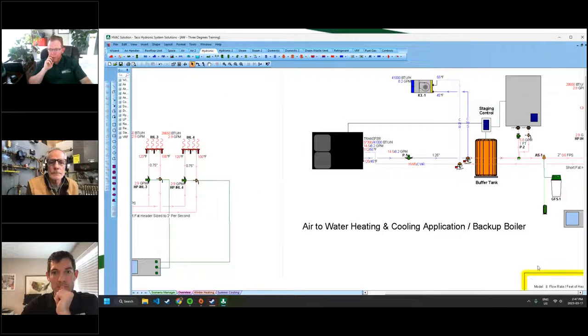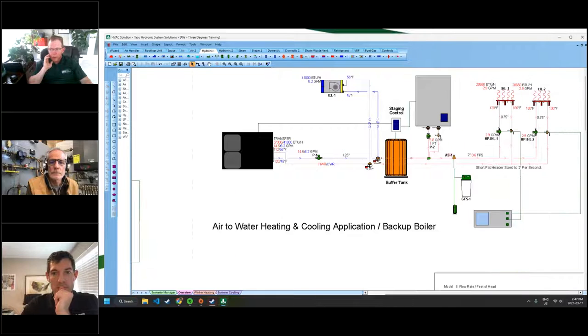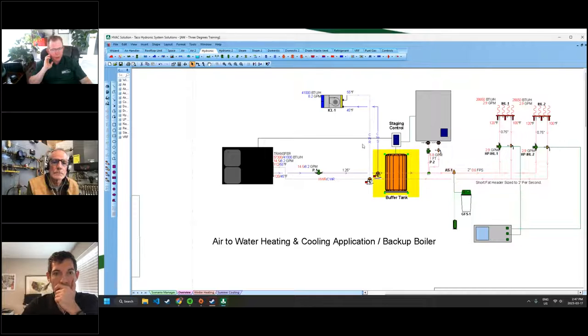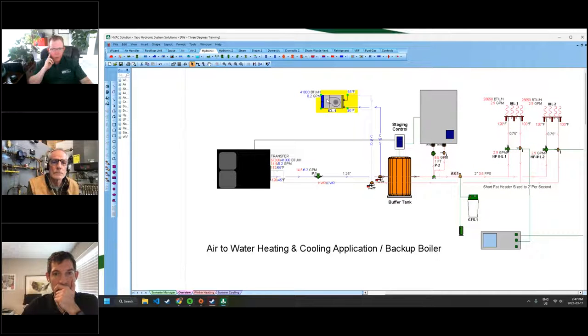This application is great because it allows us in this scenario to have heating in the buffer tank. So this buffer tank can be heated. This air handler can take care of cooling. But the other nice part about this is you don't ever have to worry about, hey, did I accidentally put chilled water into this radiant floor? There's pretty much no opportunity for this tank to get charged with cold water. And then we start having issues with dew point and sweating that's happening in the floor.